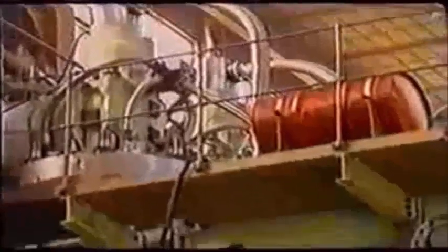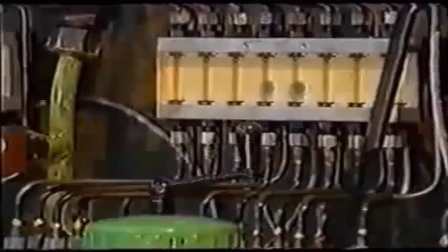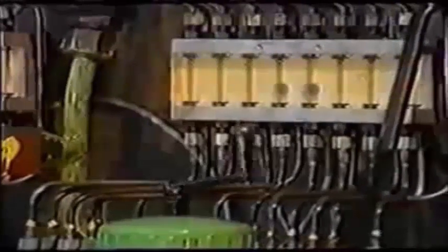The way an engine has been run in after commissioning or an overhaul is critical to establishing good cylinder lubrication. A good run-in procedure will create a good wear-in of the cylinder liner and piston rings. A good seal is obtained between them where a thin oil film provides reliable and effective lubrication. To achieve this running-in performance, a running-in cylinder oil may be used.